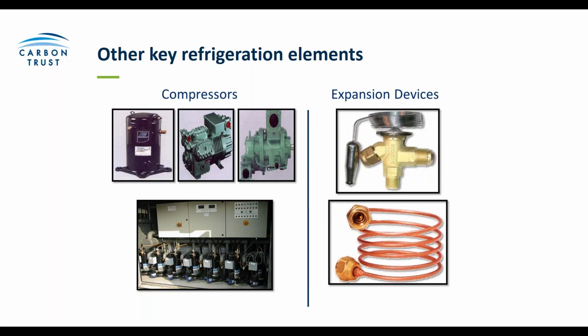It's often prudent to use multiples of compressors in your refrigeration system to improve the part load operation. So a compressor will be more efficient when it's working at full load. So having multiple smaller compressors working at full load is more efficient than having a larger compressor working at part load. And on the right hand side there, you can see the expansion devices. So these are the valves that will use very little, if any, energy. So you won't see necessarily a big opportunity for energy savings there.